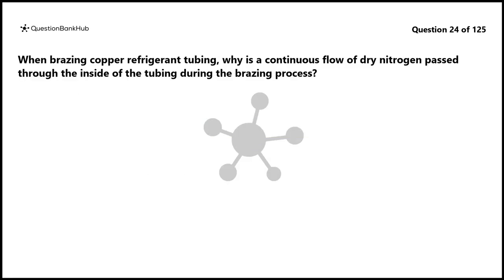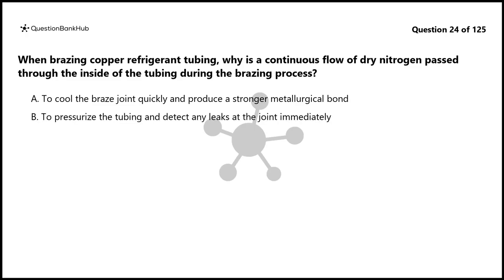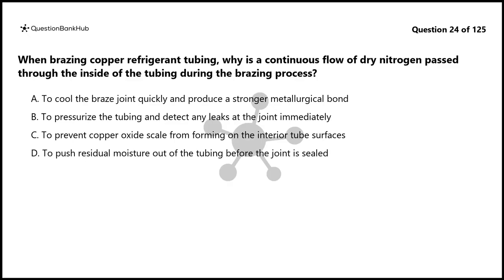Question 24. When brazing copper refrigerant tubing, why is a continuous flow of dry nitrogen passed through the inside of the tubing during the brazing process? A. To cool the braze joint quickly and produce a stronger metallurgical bond. B. To pressurize the tubing and detect any leaks at the joint immediately. C. To prevent copper oxide scale from forming on the interior tube surfaces. D. To push residual moisture out of the tubing before the joint is sealed. The correct answer is C.